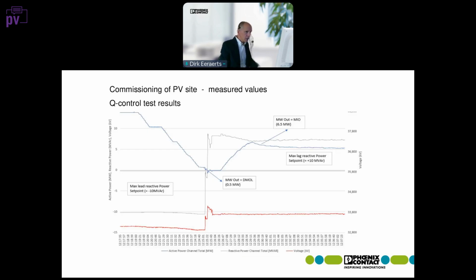So here you see the gray curve, that is reactive power, and in this test we have to go from maximum negative to maximum positive as fast as possible. And you see when that is done, so this gray curve that flips from negative to positive, there is an impact on the voltage. The voltage goes up by about 1 kilovolt, and that is really the link between reactive power and voltage that Birgit also talked about when we talk about the characteristics.